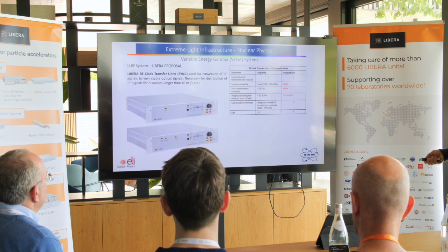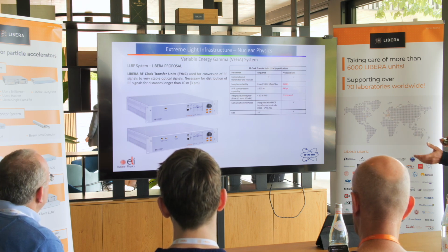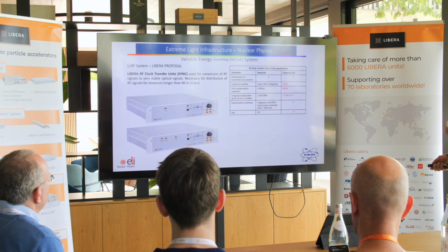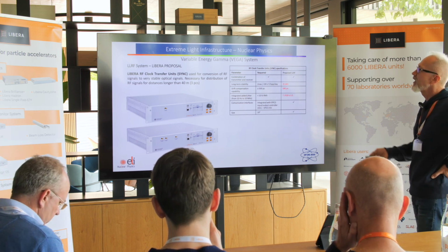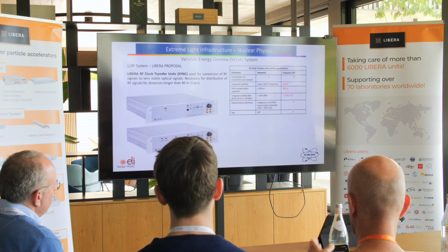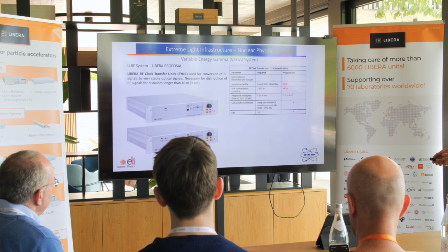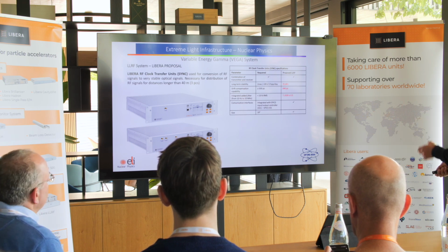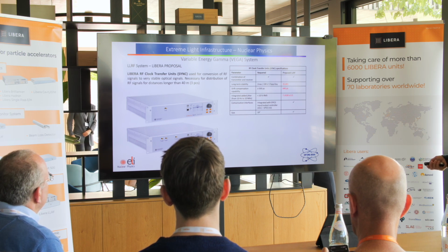And this is the last type of unit, clock transfer units, which we need because we take into consideration the distances are longer than 40 meters. We understood that it's better to use optical fiber equipment to transfer the reference signal. So we got these 3 pieces of equipment to transfer the reference signal over longer distances between those 3 chambers where the racks with the Libera equipment are going to be placed.